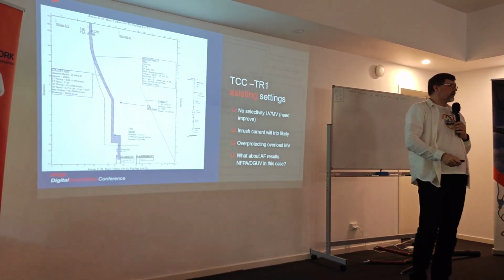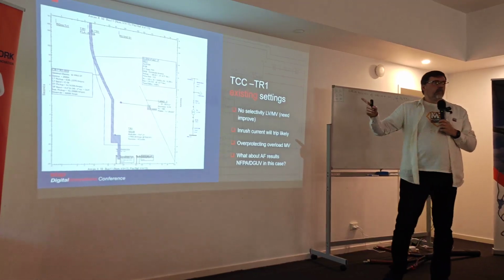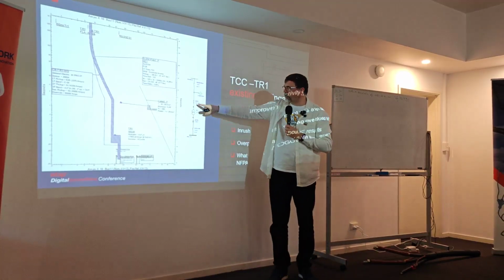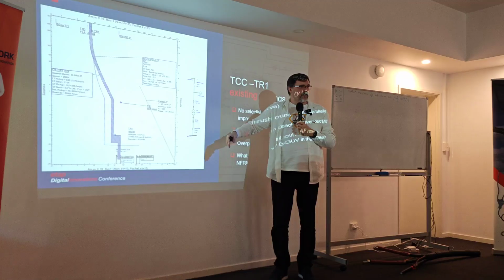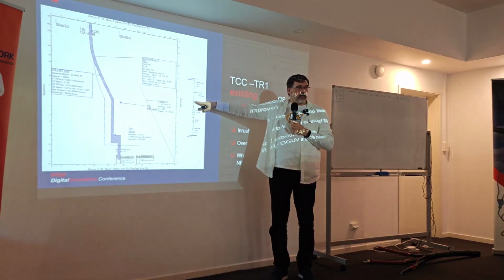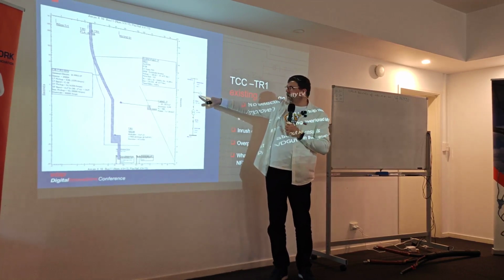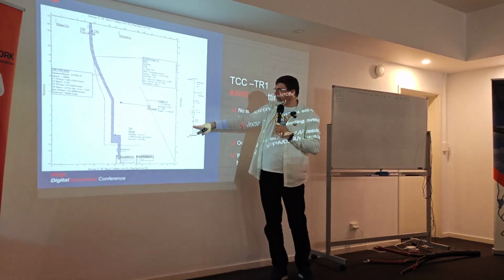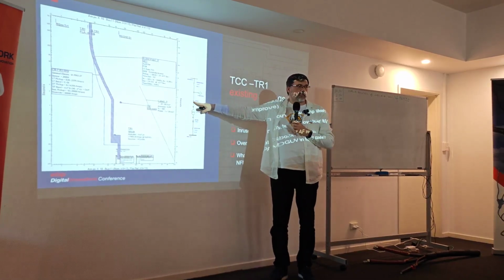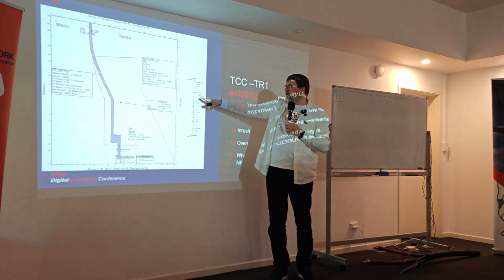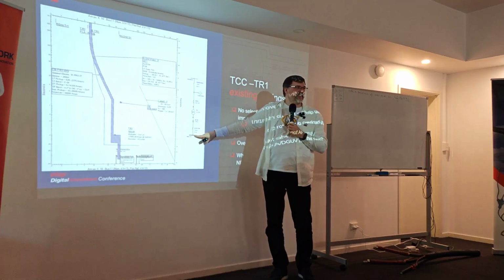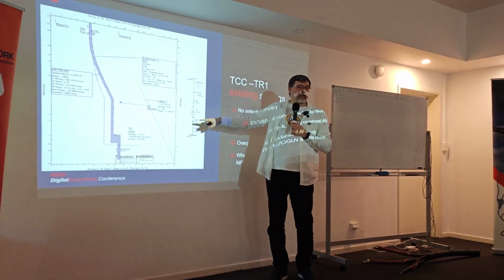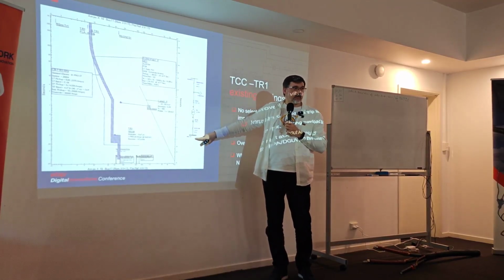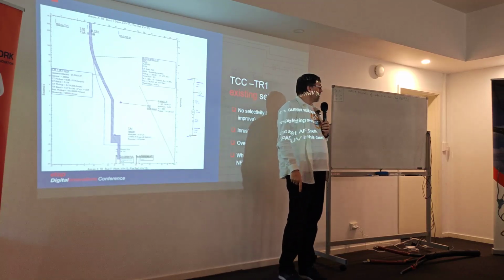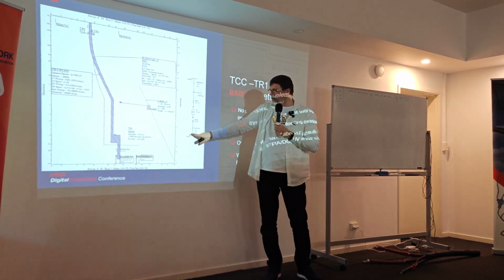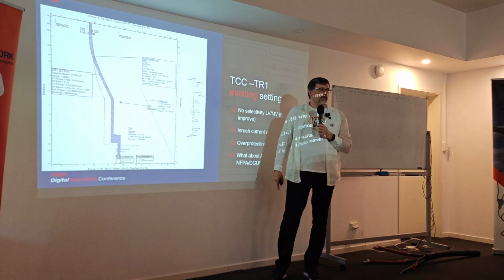I don't know if you see another problem behind it, if you are not selective as well. Because the biggest problem is not that it will trip. The biggest problem is to find out what actually trips. That's what we had on the cables yesterday. If your cable is damaged here, and this relay trips, then you expect the problem to be somewhere here, yeah? If you have 5 meters of bus bars and 10 meters of cables, it's easy to find. On a transformer, it's harder, yeah? So if this trips because you have a fault here, you will spend quite some time looking for why. If this trips because it's selective on this bus, and you go to the low voltage one and see, okay, I see why it trips, or it took me half an hour to find out, but I know it's supposed to be somewhere here, yeah? Because we know things are selective, or they work properly.